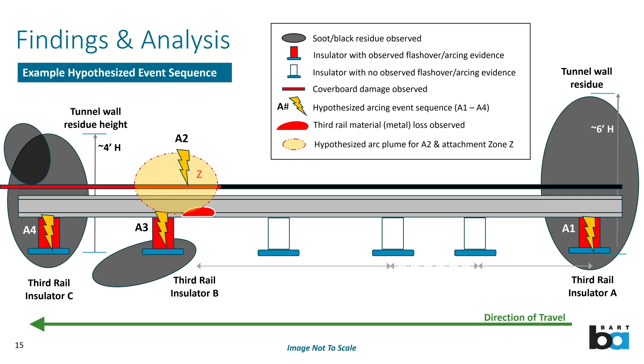On the top right is a photo of the cover board, showing a stepped profile on top where it's evident the damage was from the top down, aligning with the area of material loss in the third rail. A hole in the third rail of that size is typically due to high energy arcing - the type of energy required to essentially vaporize that metal. Beneath it are the remnants of the insulator, with the soot deposition pattern visible on the track slab, and to the left is how it looks at C, directly behind where the insulator stood.